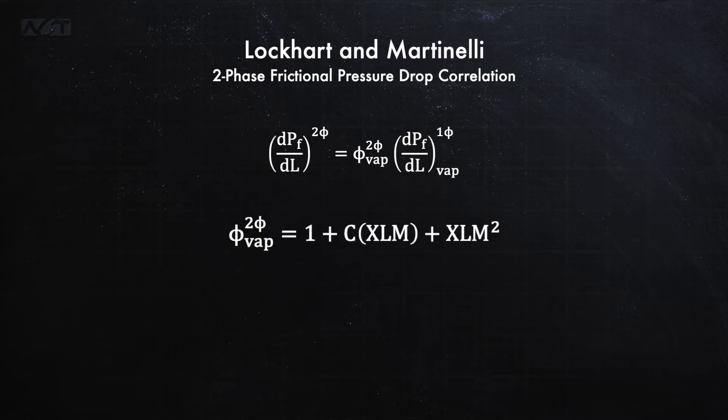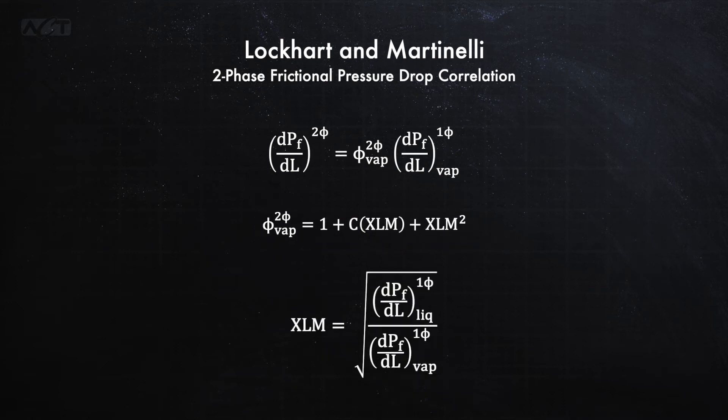The correction factor is calculated using a flow-dependent C parameter and another parameter known as a Lockhart-Martinelli parameter. The Lockhart-Martinelli parameter is the square root of the ratio between the pressure drop of the liquid portion of the flow and that of the vapor proportion of the flow. I won't get into all the details of this method here, but it's really well documented in the literature.